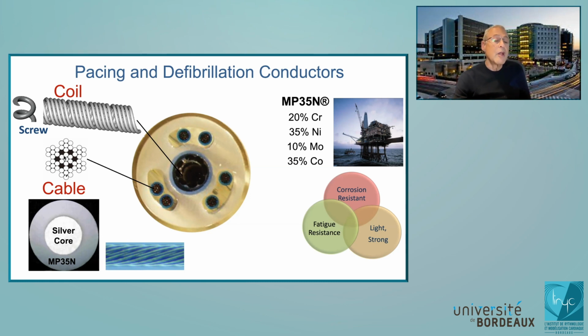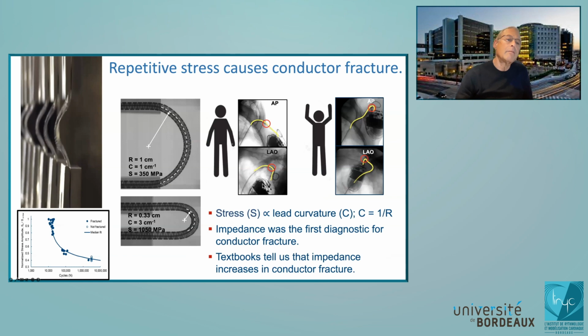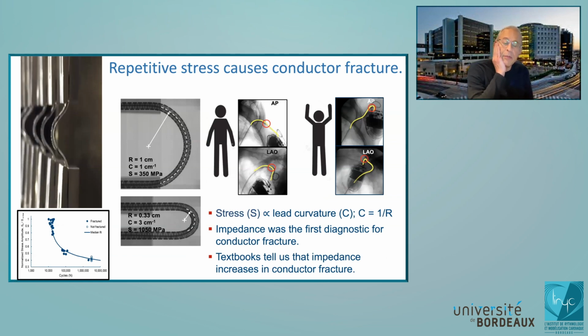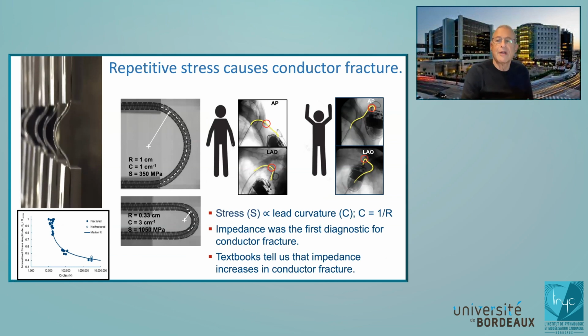And so the difference between a shock conductor or shock cable and a pacing cable is not the design of the filars or tensile strength. It's whether they've paid money to put extra silver metal in there to allow the shock to be transmitted. That's all I want to say about this. Questions about the metallurgy? Good.